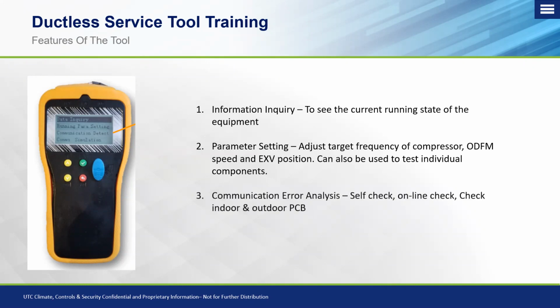You have a communication error analysis on here. This is where you're going to use your L1, L2, and S, or your L, N, and S connections to perform a self-check on the tool to make sure that it's working properly, and an online check to make sure that a unit, whether it's one or multiple, is actually online and responding. And you can check indoor and outdoor PCBs by wiring through an outdoor bus bar or an indoor bus bar to make sure that they respond to commands sent from the tool.